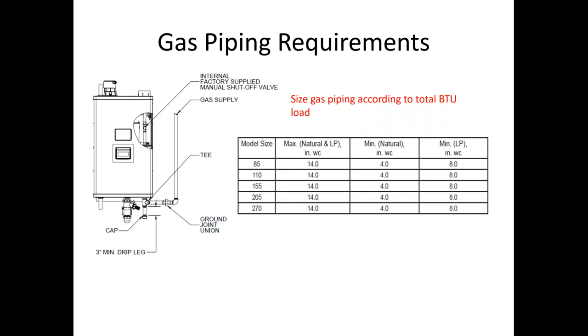Minimum inches of water column for LP is going to be 8, and natural gas is going to be 4. Too high of gas pressure also results in some problems. With gas pressure that's too high, you end up with some whistling and weird combustion noises. Also, if there is an inline regulator, we want to try and keep that inline regulator approximately 10 feet away from the boiler, so you don't wind up with any of the reverberation from the regulator.